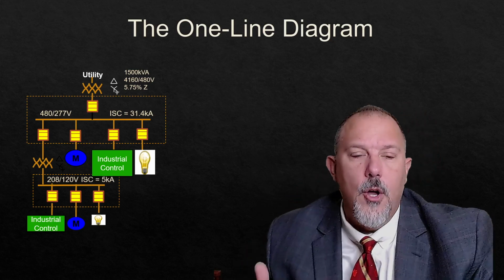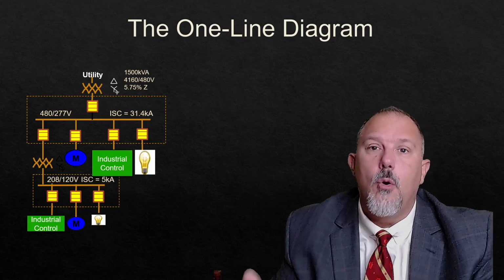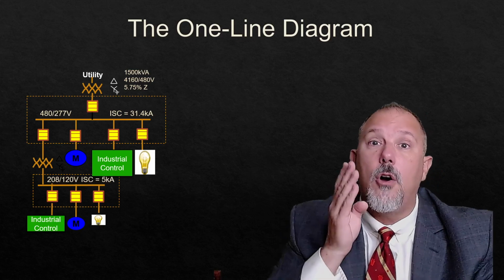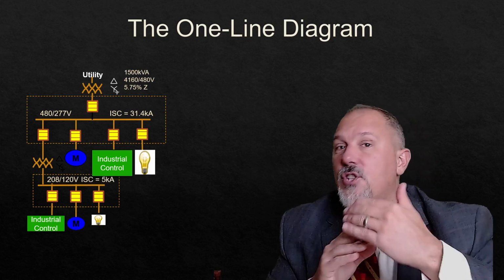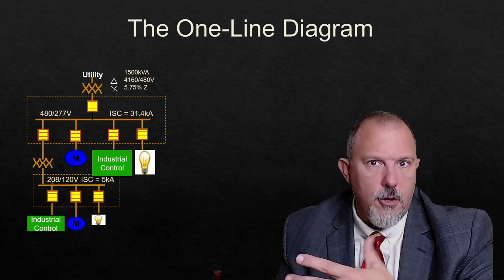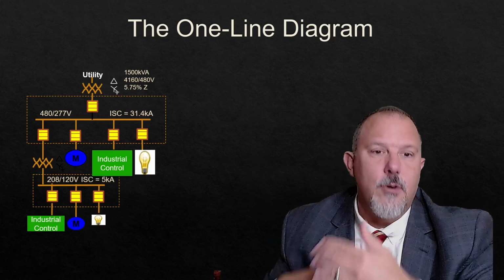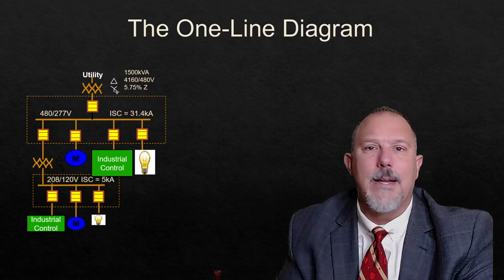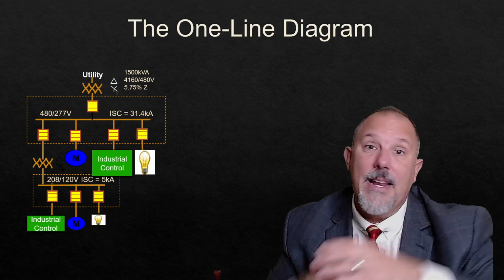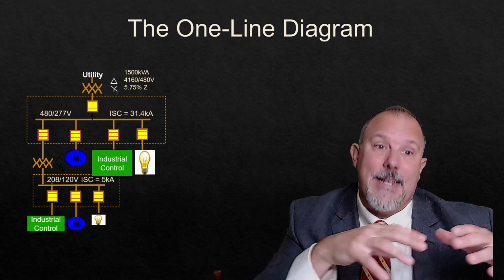You need to know the motors. How big are the motors? What's the horsepower rating of the motors? If you have an X to R ratio of the motor, a percent impedance of motors for large motors. You need to know as much information as you can put on a one-line diagram, the better off you are. That information is going to go into calculating fault currents.